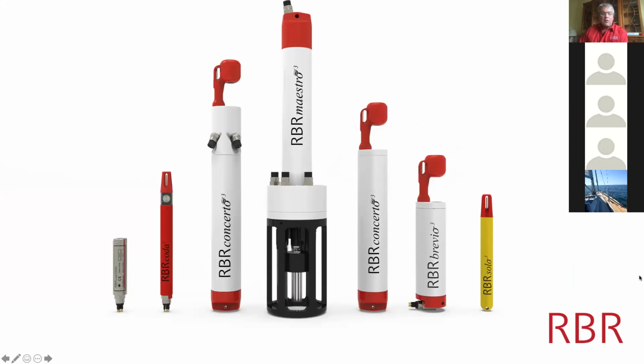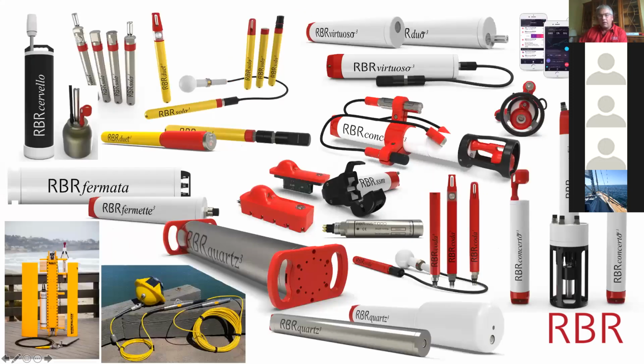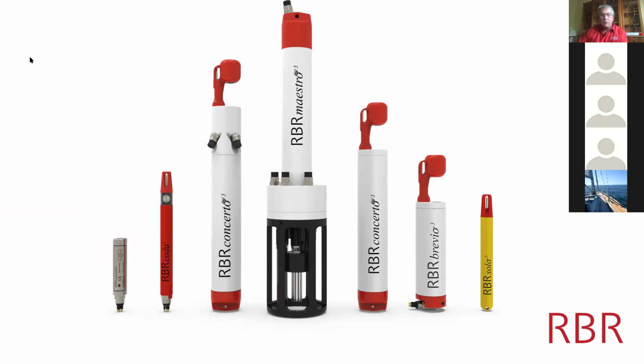Here we have a large range of equipment coming from RBR, with the sensor just with the connector here. After that we have the small logger with one parameter, and then we move to the other ones, the 2 channel, 5, or 10, moving to the Concerto and the Maestro with a large multi-parameter sensor, a large CTD.